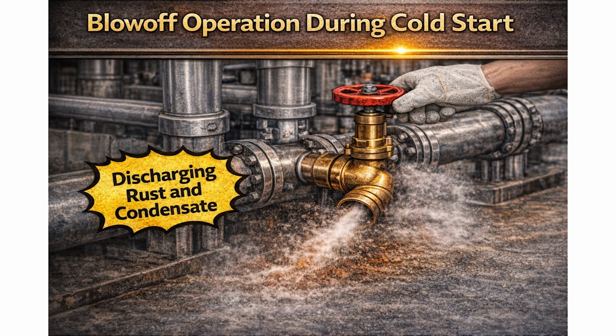But in some factories, especially smaller plants or plants with frequent start-stop cycles, this procedure is not clearly separated from normal operation. Steam is introduced immediately, without blow-off, and this happens repeatedly. Under these conditions, condensate remains inside the piping, and in that situation, an orifice trap becomes difficult to apply.